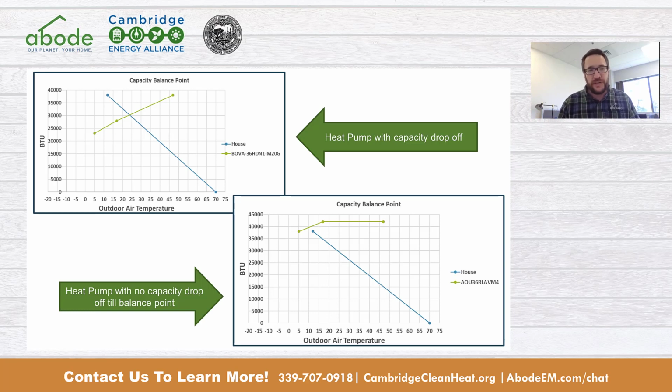And one thing that is important to know is that when the home's load surpasses the heat pump's capacity, it's not like anything catastrophic happens. If you have the heat at 70 degrees, and the heat pump can't keep up, your house doesn't become 35 degrees. It becomes 69 degrees or 68 degrees or 67 degrees. Oh, and now the sun's shining, and now it's 68, 69, 70 degrees. If you are sizing the system really close to the building's design load, nothing horrendous is ever going to happen.